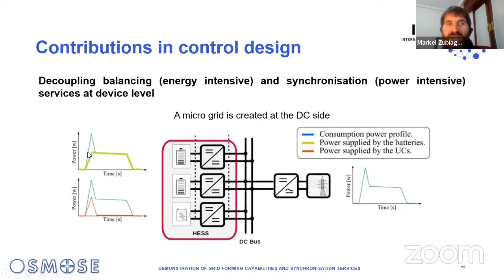These settings allow that when the AC side demands a fast, huge active power, the ultracaps react quickly and give the peak, while in the long term, since they don't control with an integral component, after a few milliseconds the battery takes over and provides all the active power.